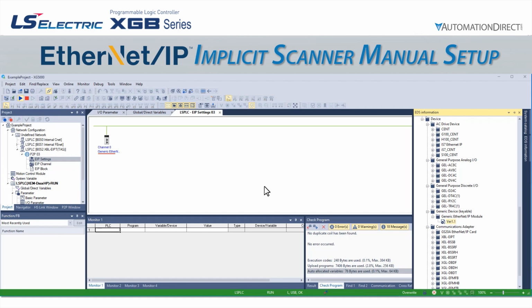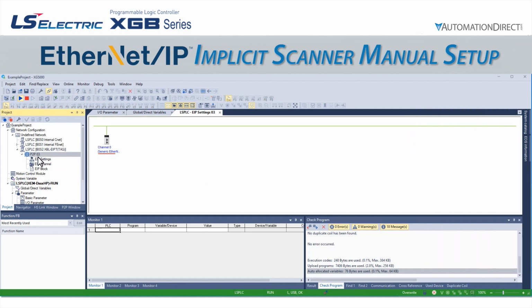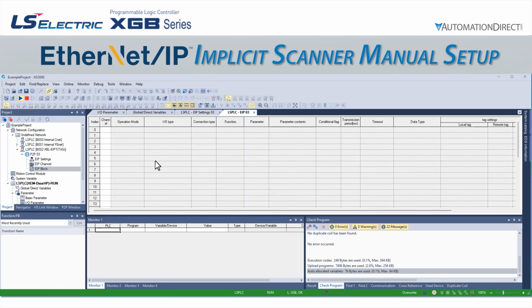Now that we have added the channel to the connection, we are ready to configure our message. If we go back to the EIPT card, and then our P2P03 connection, we can double-click on EIP block, and the software opens the LSPLC EIP03 tab. The channel for this message is 0 since we set up our adapter the same as when we used the GS20 EDS file. This time, however, we have several options for I/O type that weren't there when we imported the GS20 EDS. This is because the generic EDS file doesn't specify the message types available the way that the GS20 EDS file did.